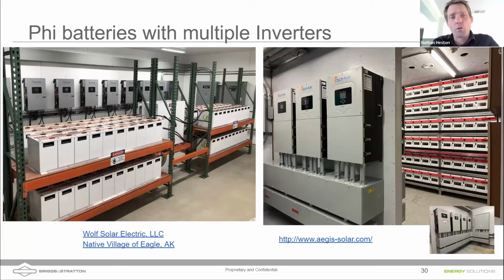I did want to highlight that for large systems, and I'm showing the installers here who submitted these to us. For large systems, both of these systems have, I believe, 7 Sol-Ark 15K inverters. It looks like those might be 12Ks on the left picture, but for large systems, it might be easier to use big bus bars and combine the batteries in a big DC combiner. And of course, when you're using multiple inverters, you want to have a single bank powering all of them. So you need that combiner. And so showing you some nice examples there with the big Sol-Ark installations.